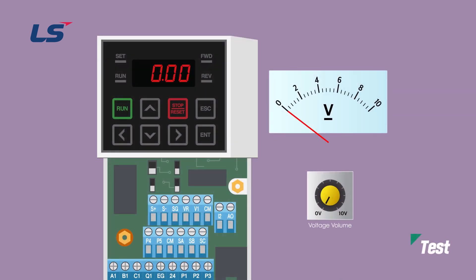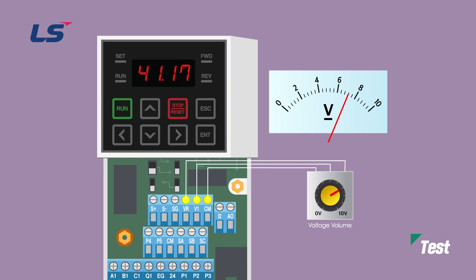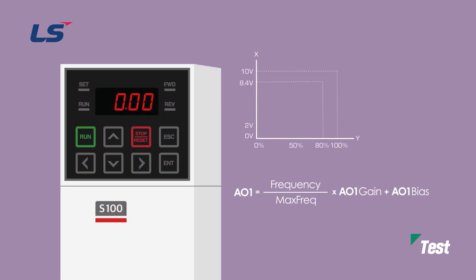Next, we will conduct the test under the parameter conditions set previously. After wiring the variable resistor to VR, V1, and CM terminals to use the internal power supply, rotate the variable resistor and check that the target frequency changes. Below 2 volts, the frequency command becomes 0 Hz. Above 9.5 volts, the frequency command becomes 60 Hz. For analog output, since bias was set to 20% and gain to 80%, a graph is drawn as shown on the screen depending on the output frequency. We learned about how to control the analog input and output of the S100.